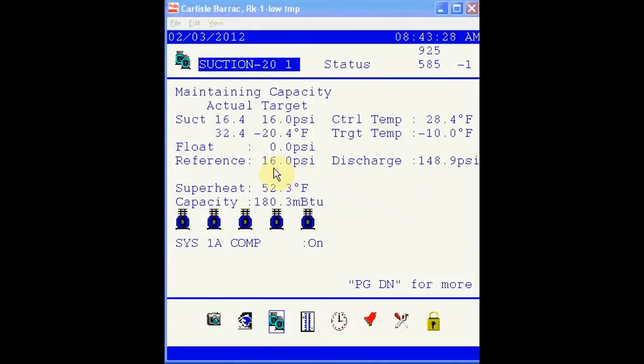This rack's basic target is 16 pounds. We know that it's not floating currently because the float adjustment is set to 0. The reason for this is that the case temperatures that are floating the suction are higher than the target temperature. As we'll see in a moment, the case that's floating the rack is actually in defrost right now. Let's take a look at how this floating is set up.